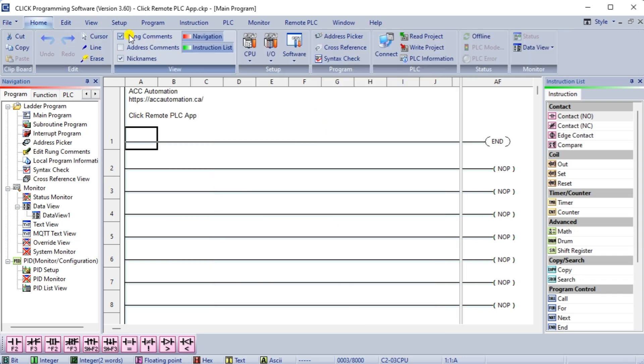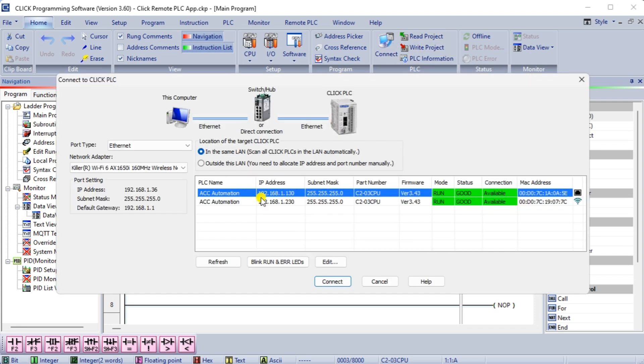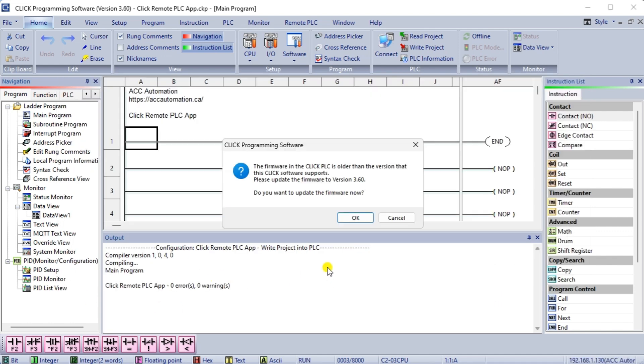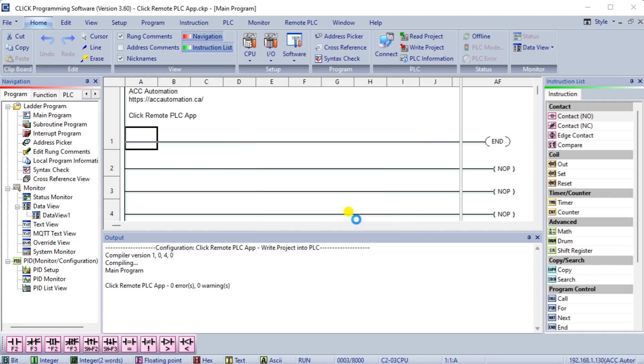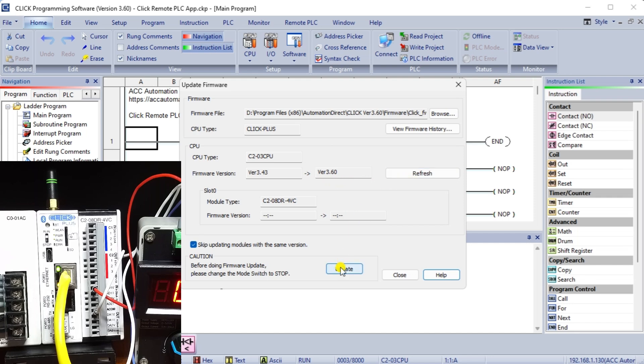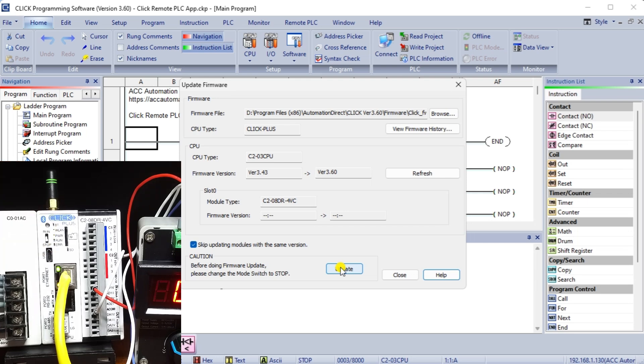Select write project from the main menu home. The connect to PLC window will be displayed. Select the PLC or method to download the program and select connect. Once the connection is established, a message will be displayed indicating that the firmware needs to be updated in the click PLC. Select OK to update the firmware now. The update firmware window will now be displayed. Ensure that the PLC mode switch is set to stop. Select update.